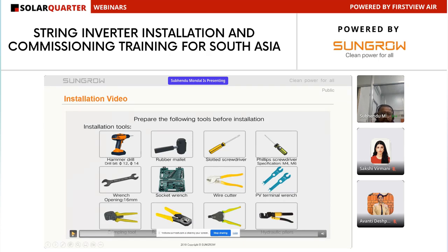So here we have to unpack our inverter box. When we open the inverter, we will find one inverter inside, and some screws for the mounting bracket, MC4 connectors, and screws for mounting the inverter. Then we have to go for preparation of tools. Basic PPE is required before installation, like safety gloves, helmet, and safety shoes. We also have to decide the place where we are going to install the inverter, and gather basic tools like a screwdriver, MC4 connector, PV terminal wrench, hammer drill, crimping tools, and a screwdriver set.